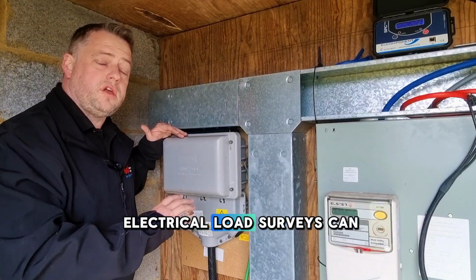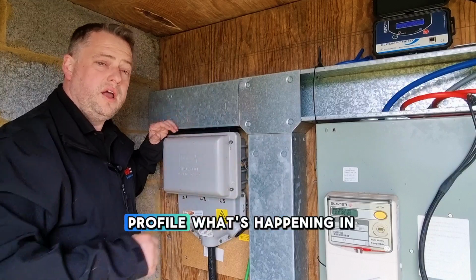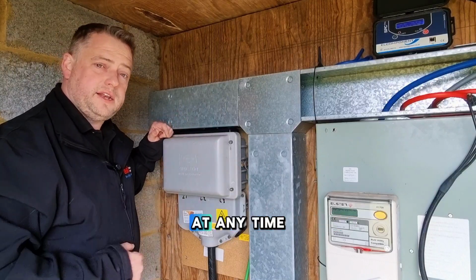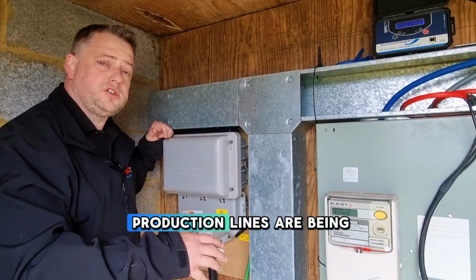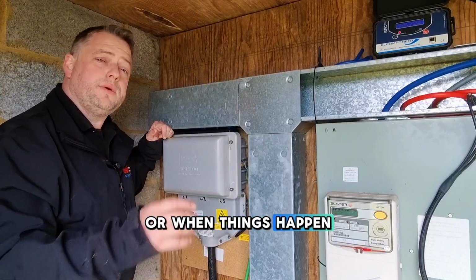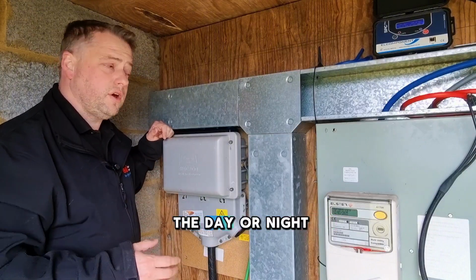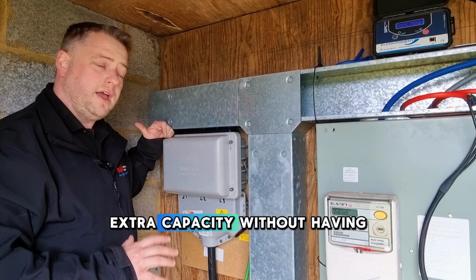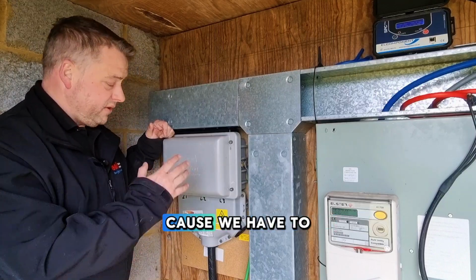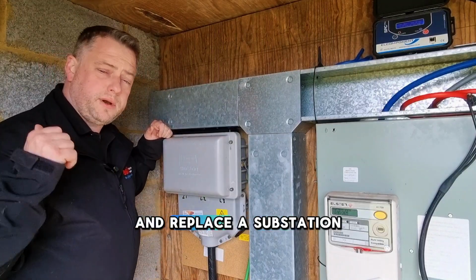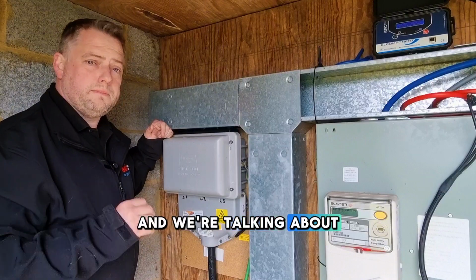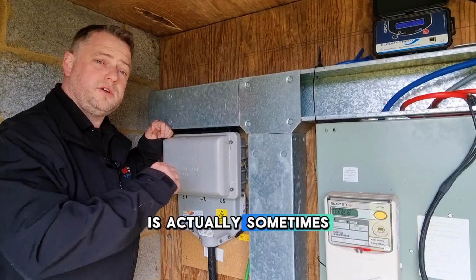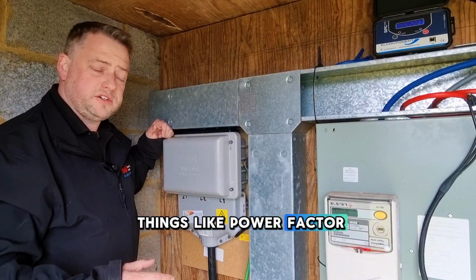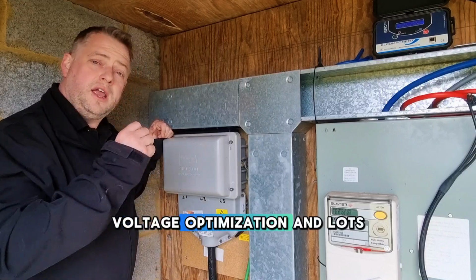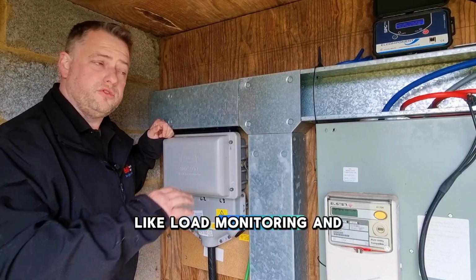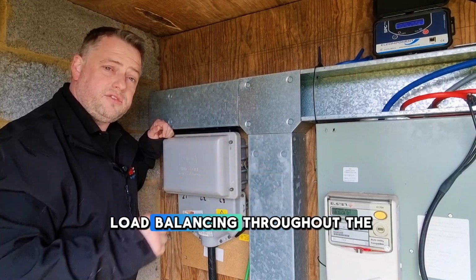That's where our electrical load surveys can really help, giving us a full profile of what's happening in the business at any time. We might want to change how production lines are run, or when things happen within the business at different times of day or night, to allow extra capacity without changing this supply. If you have to replace this cable into the building and replace a substation, that's a major cost to a business, whereas efficiency can actually come from things like power factor correction, voltage optimization, and other tools like load monitoring and load balancing throughout the system.